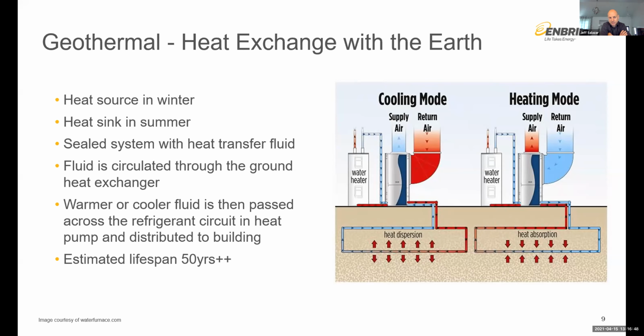The reason we put an antifreeze or a heat transfer solution in there is because the heat pumps are so efficient that they have the ability to remove and extract the energy. If you can imagine the ground's at 10 degrees C and we circulate a slightly cooler fluid into that ground loop, when it comes back and that heat pump removes that heat energy, the fluid going back into the ground would be close to 0 Celsius, which is near the freezing point.